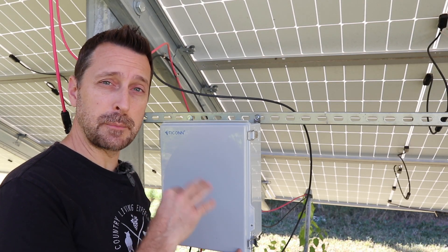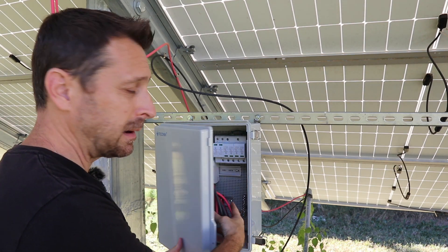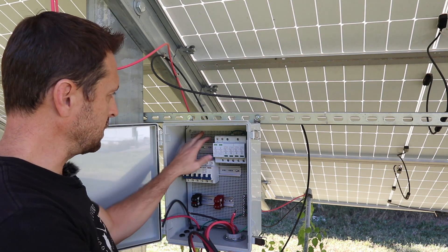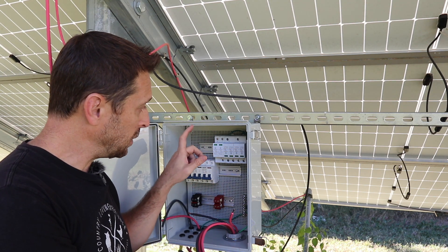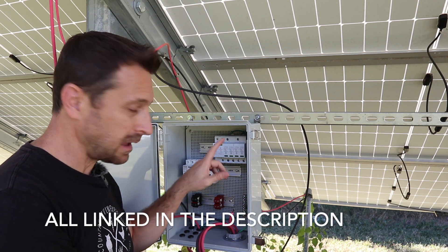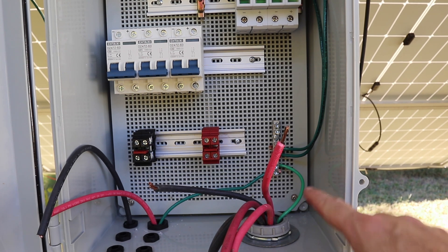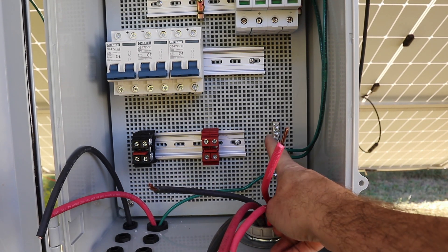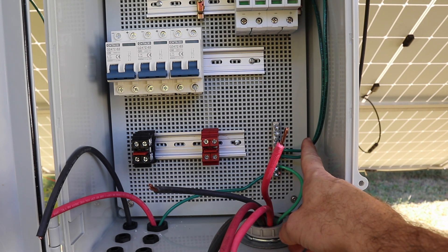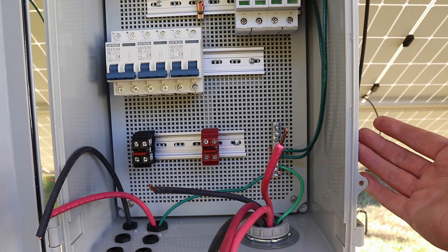Let me show you what we've done so far in the box. I'm using this plastic Ticonn box, which has a grid on the back where you can screw in DIN rails to put on your breakers, your surge protection, and whatever else you need. I like these plastic boxes — they obviously don't have to be grounded like a metal box. I do have a grounding bar here, but that's for our electrical grounding conductors.